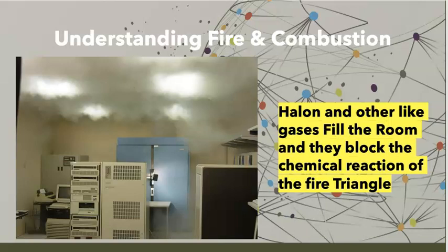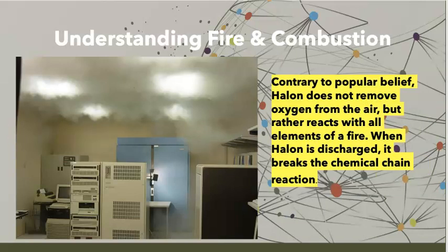Contrary to popular belief, halon does not remove the oxygen. CO2 does, and some of our other gases we might use, but it reacts with the elements of the fire. When the halon is discharged, it breaks the chemical chain reaction. This accounts for most of its firefighting properties. The other properties come from a cooling effect. We actually do get some benefit from the CO2, which is often used to push the halon into the room.